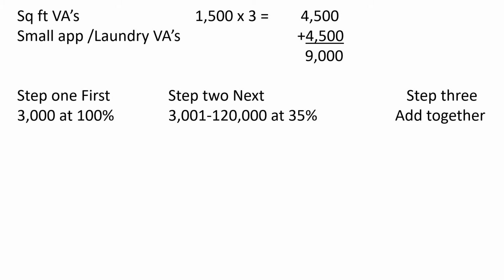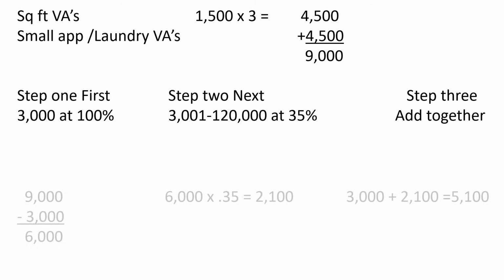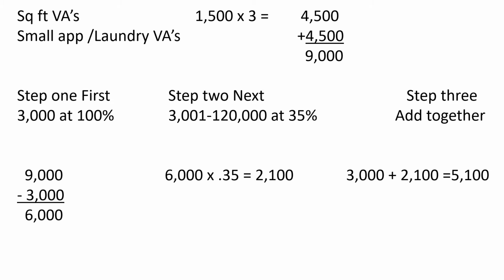Now we need to do our demand factors for the first portion of our load calculation. So step 1, we have the first 3,000 at 100%. Step 2, we do the next 3,001 up to 120,000 at 35%, which is going to allow you to do another 117,000 total at this 35%. And then step 3, we're going to add those back together. Okay, so we take 9,000 for step 1. We're going to minus the 3,000 that we need to do at 100%. That's going to give us 6,000. Now we take that remaining 6,000, we're going to multiply that by 0.35, and that's going to give us 2,100 VAs. Now we need to add those back together. We take 3,000 and we add 2,100, and that's going to give us 5,100 total general square foot and small appliance laundry circuit VAs for this load calculation.